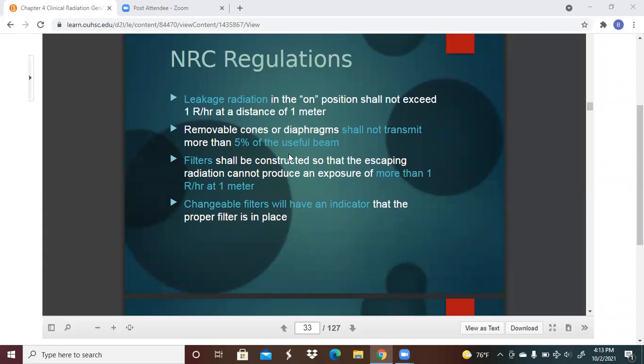The NRC regulations are that leakage radiation in the on position shall not exceed 1 Roentgen per hour at a distance of 1 meter. Removable cones or diaphragms shall not transmit more than 5% of the useful beam. A filter shall be constructed so that the escaping radiation cannot produce an exposure of more than 1 Roentgen per hour at 1 meter. Changeable filters will have an indicator that the proper filter is in place.